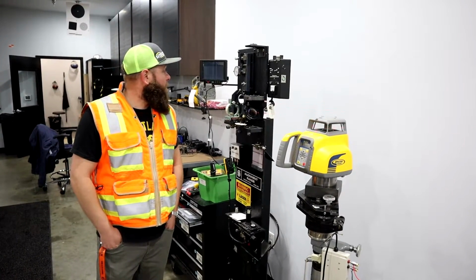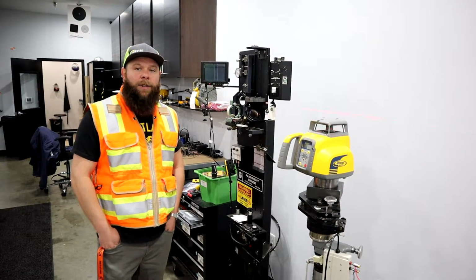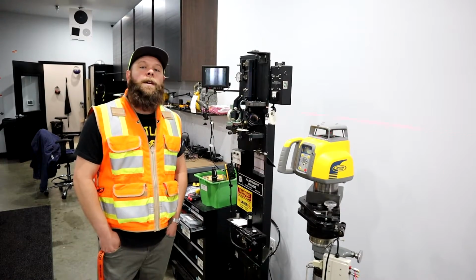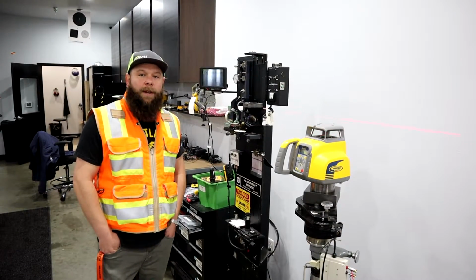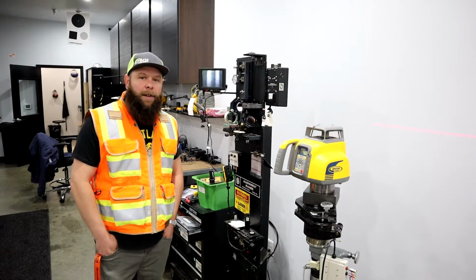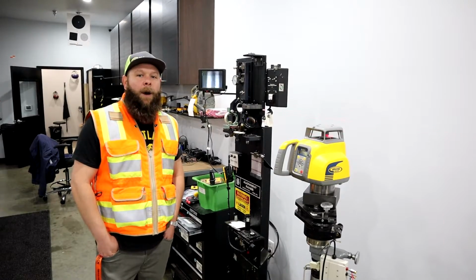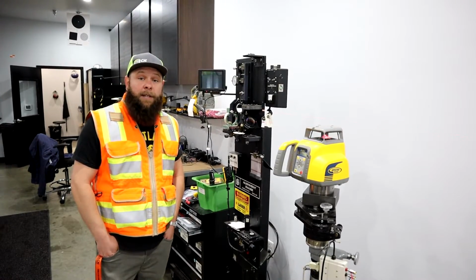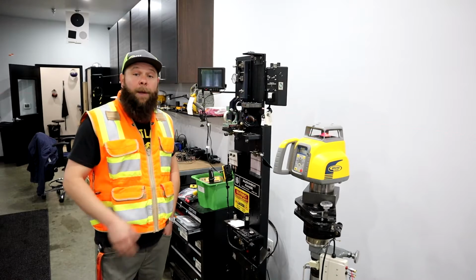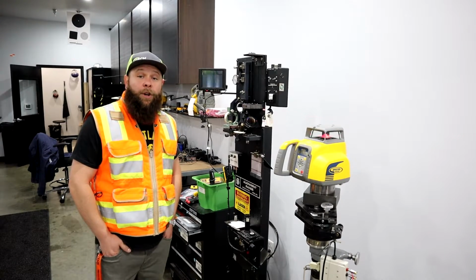So if what we did outside shows that your laser is out of calibration, there is a field calibration, but we don't really recommend it. You can get your laser beams way further out. We do recommend that you come drop it off at SITECH, and we'll put it on our range and calibrate it to manufacturer specs.